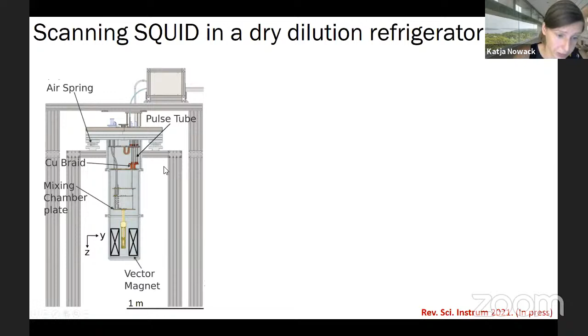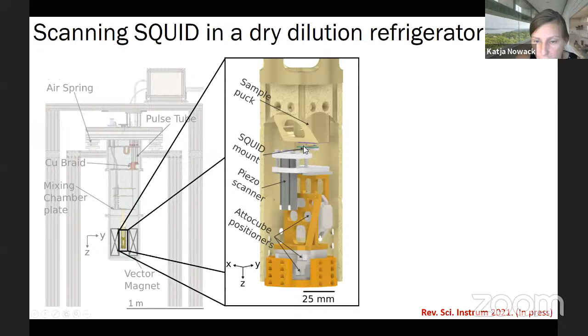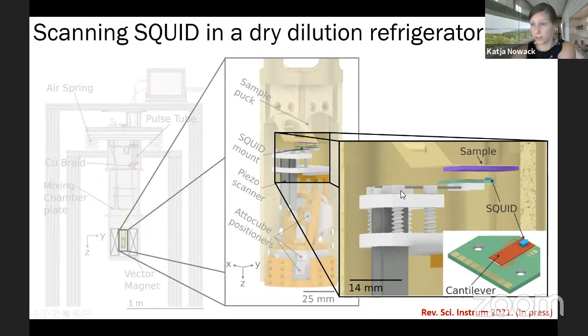The instrument in which we are doing this is a dry dilution refrigerator, and you see a cut drawing of our system right here. Here you see a zoom-in of the actual microscope that we use. There is a range of piezoelectric coarse positioners, and here is our scanner. At the far end, this little board carries the SQUID. You can zoom in one more step, and then you really see the SQUID that's brought close to the sample by approaching it with this piezoelectric bender that essentially moves up and down.